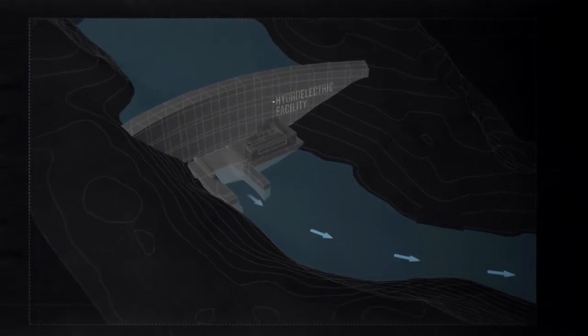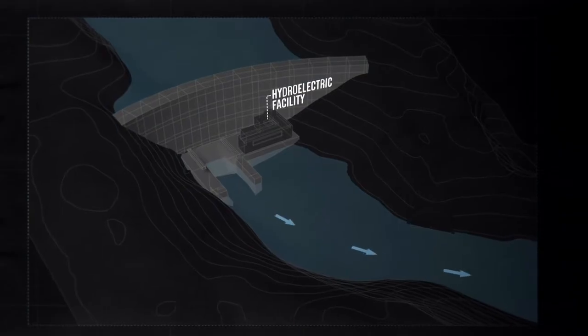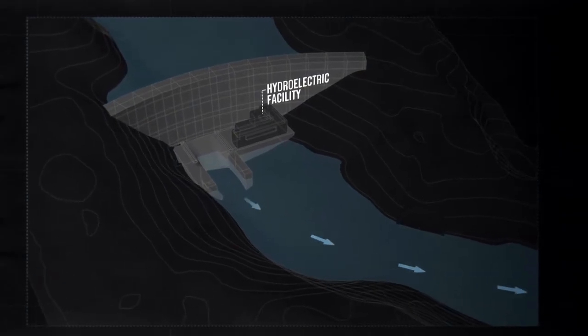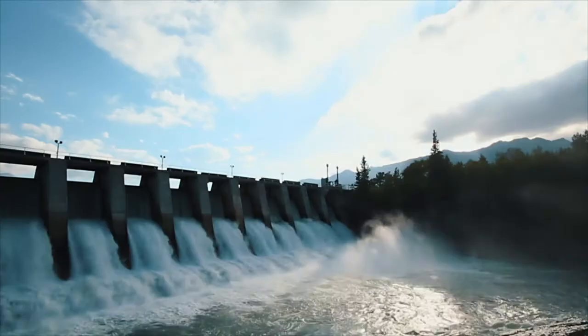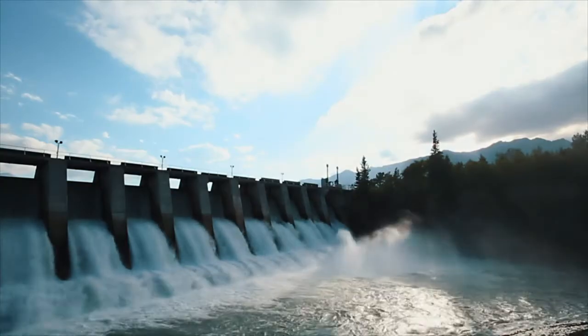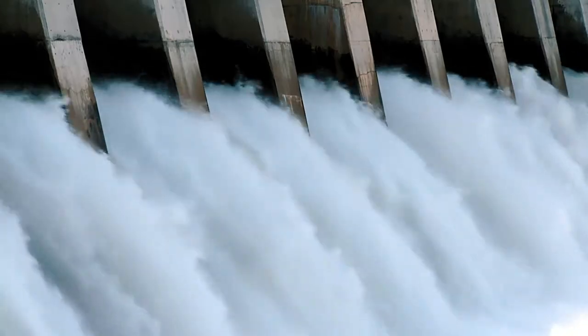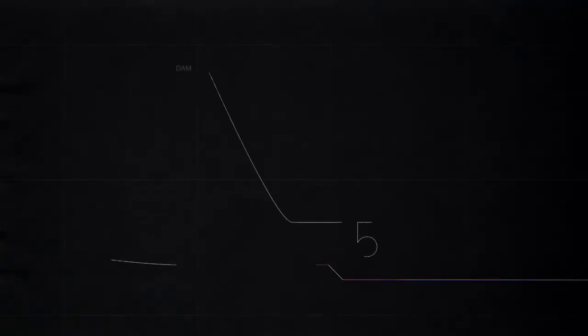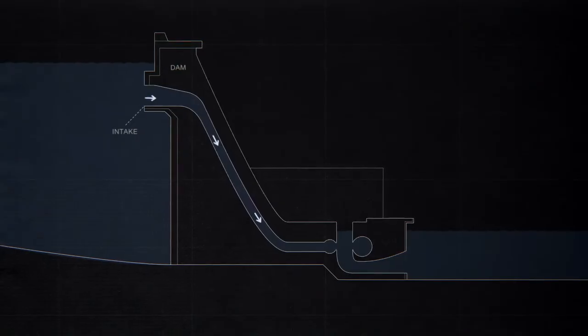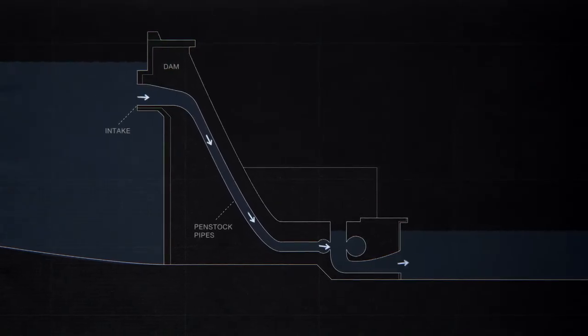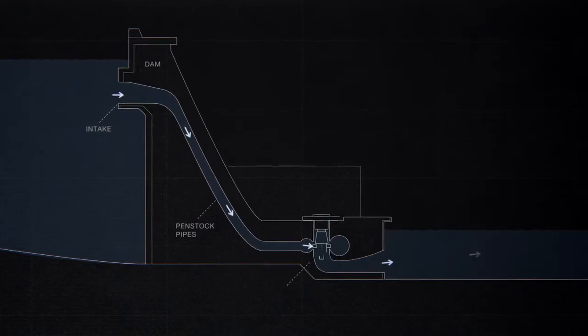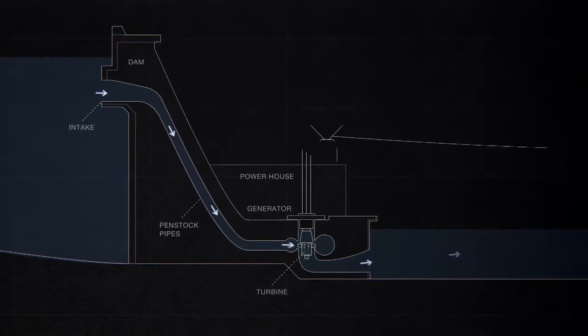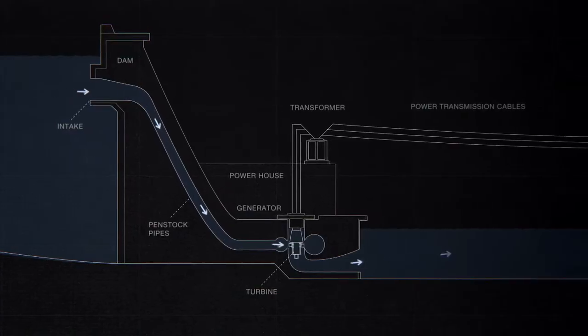The hydroelectric facility can be built after the dam is completed. Once the foundations are built, the turbines themselves are constructed on-site and installed, and the remaining structure is built around them. In a hydro scheme, the water comes through the intakes in the upper part of the dam and then flows down into wicket gates, which control the flow into the turbine. The moving element of the turbine is connected by a shaft to the electrical generator.